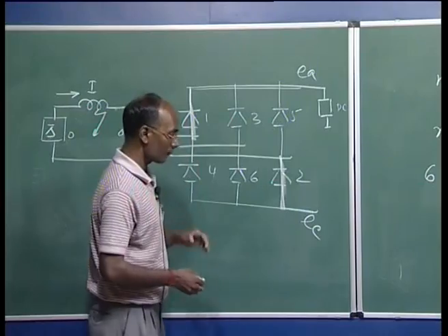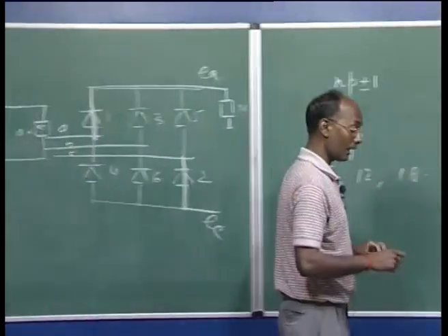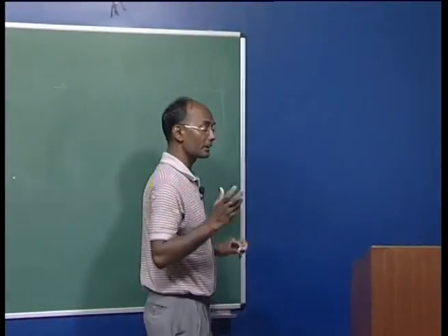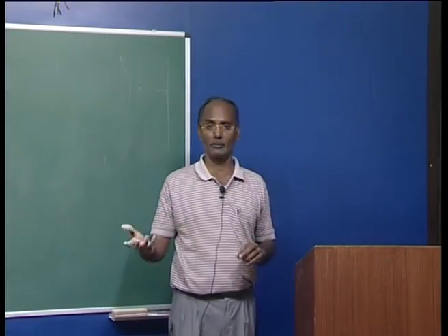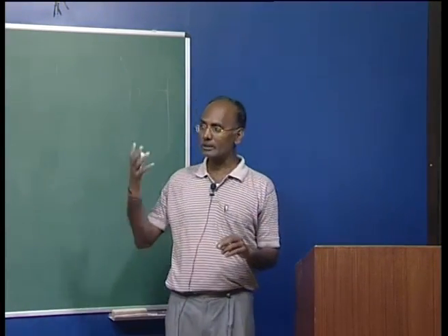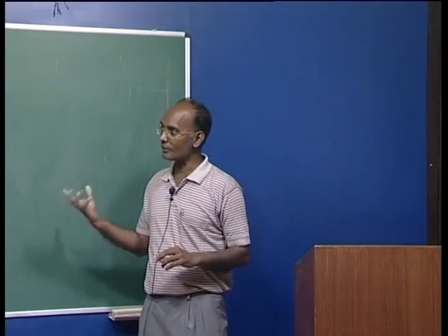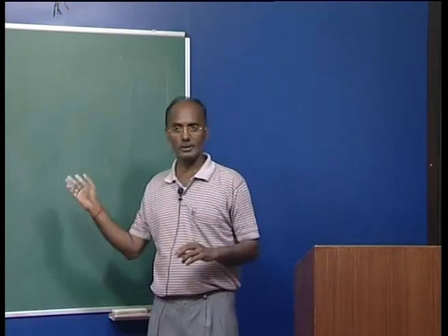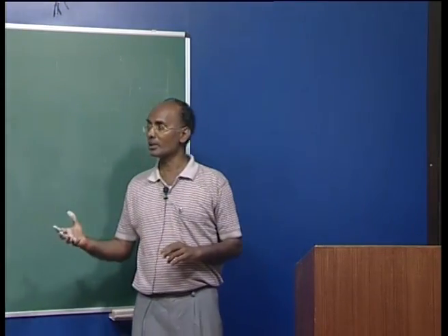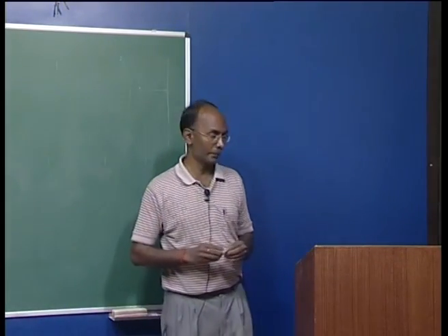Then another component which I discussed, the transformer. And I showed that this transformer is not a simple transformer, meaning not an ordinary transformer used in the AC system. It is specially made; OLTC transformers are used at both converter stations, and it should withstand the harmonics as well.